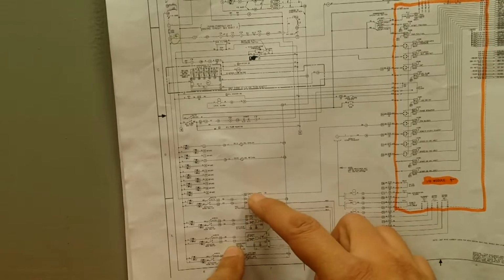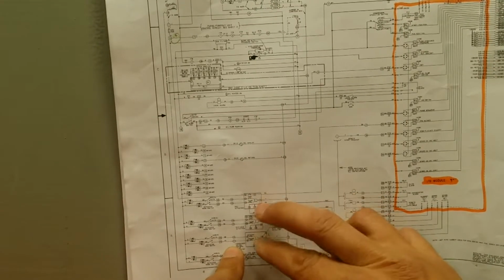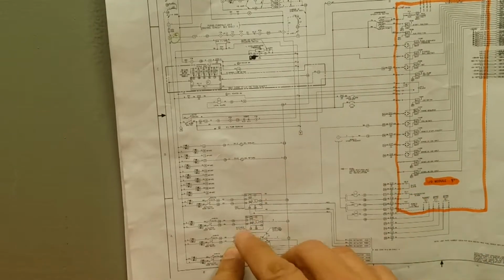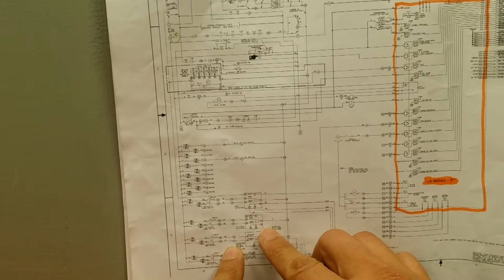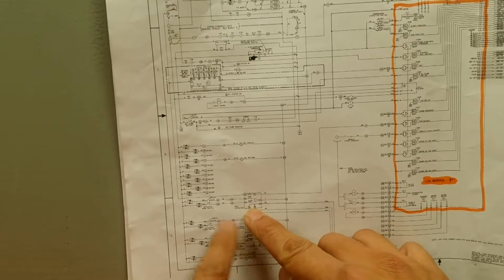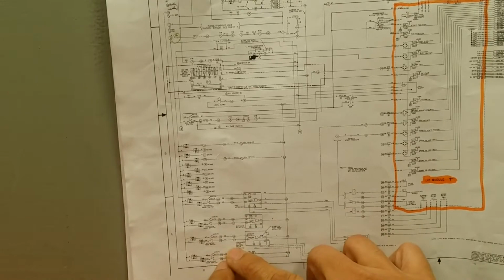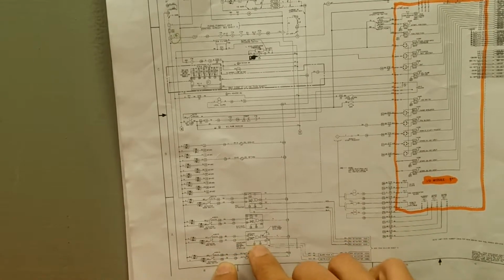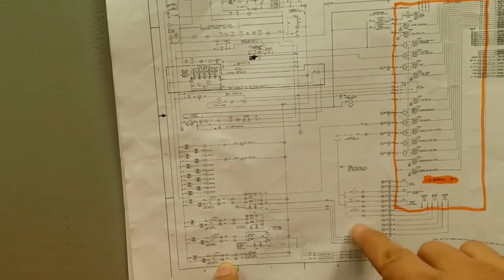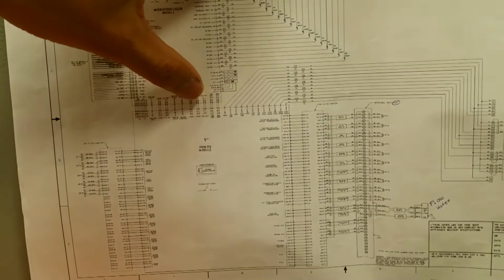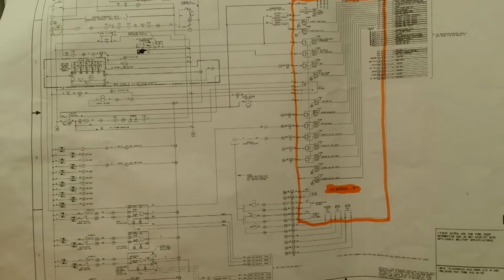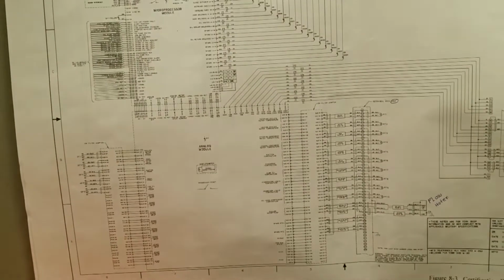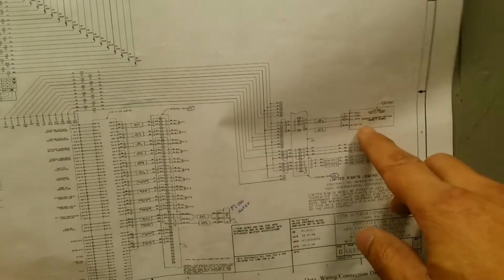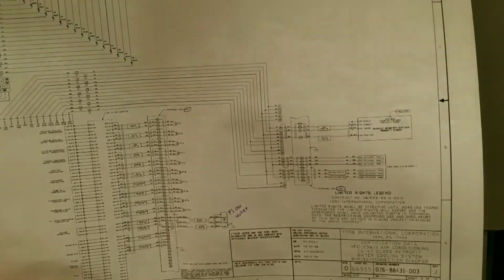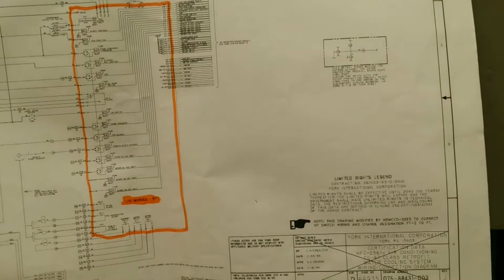The diffuser actuator and the PRV valve are of the same type, so this valve and this valve can be interswapped. The difference is that for the diffuser you wouldn't be using the built-in potentiometer, whereas there is a built-in potentiometer in the PRV and the CWC valve. And this input over here goes over here, and eventually it makes it into the analog module, which I'll talk about later. It's safe to say that whether it be a potentiometer or a proximity switch, it lets you know the position in percentage, or whether those valves are open or closed.